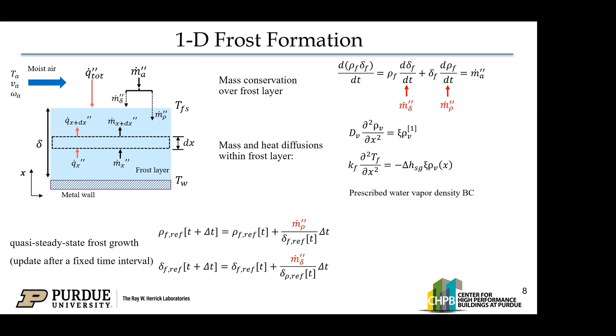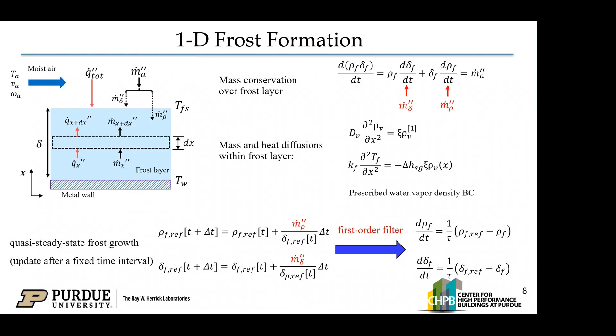Because when we derive these equations we neglect the energy storage, it's actually a quasi-steady state analysis. So we update the frost density and thickness after a fixed time period. You can consider this as a discrete system. But later we will see that we want a consistent model structure where density and thickness are state variables for a frost layer, either at frost formation or melting. So we apply a first order filter: from the frost formation model we calculate the reference values, and the actual state variables track those reference values.